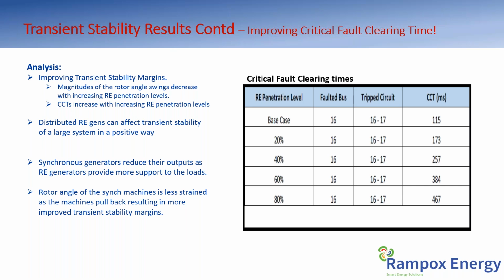Further analysis will show that if you look at the critical fault clearing time on your remaining machines, you start seeing that it improves. The base case gives 115 milliseconds. At 20%, you see 173. At 40%, 257. At 60%, 384, and then at 80%, 467 milliseconds.